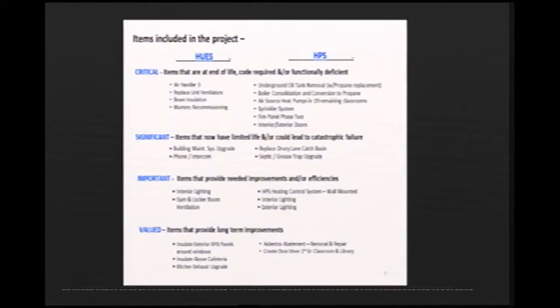The locker room ventilation: right now the locker room is bringing in cold, fresh air and conditioning it for the locker room, and we're bringing in cold, fresh air for the gymnasium. Our idea is to take the air from the gymnasium, which is kept at a lower temperature, and recondition it for the locker room before exhausting it. That'll precondition the air and lower our energy bills. And again, this is a very short payback, very easy to do, doesn't cost much, and saves quite a bit of money. Another thing this is going to do is help prevent mold. Anytime we can help prevent mold, that's going to be in our benefit.